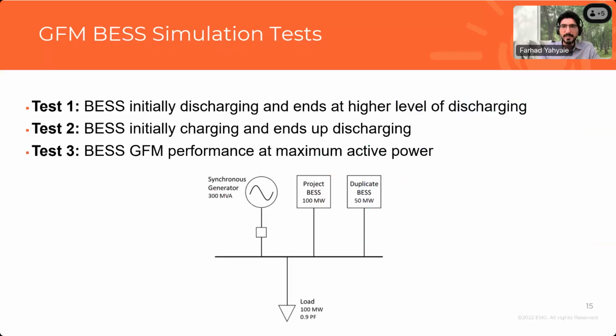Next slide, please. The test system used in this white paper is pretty simple, as shown in this diagram. It comprises a BESS project rated, let's say, 100 megawatts, and a duplicate BESS project using the same model but rated at half the capacity, 50 megawatts, plus a load equal to 100 megawatts, and a synchronous generator and infinite bus system rated about 300 MVA. In all the tests, the synchronous generator will trip after initialization of the case, and the behavior of the BESS GFM and GFL models will be evaluated.